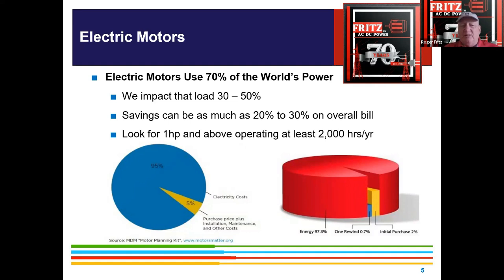So it consumes a lot of power, and it ends up being about 70% of the power that the world uses, which a lot of people may or may not know. Or they try to go, well, I'm putting in lighting, so we're getting efficiency. Well, lighting most of the time is only about 10% of the total load in a factory. And so it's kind of minuscule how much they're really going to save. A lot of times they'll put in new lighting, they won't see much change in their power bill. Whereas when you put it on electric motors properly applied, it does have a very large impact.